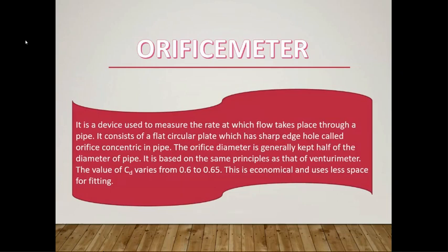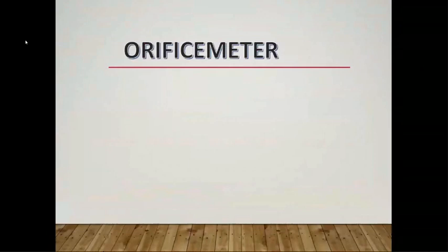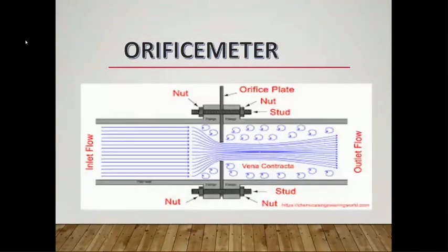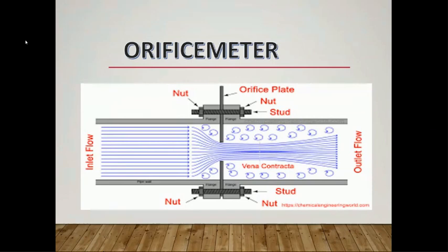The orifice meter is based on the same principle as the venturi meter. The value of Cd, the coefficient of discharge, is the ratio of actual discharge to theoretical discharge from the orifice, and varies from 0.6 to 0.65. It is economical and cheaper than the venturi meter and uses less space for fitting. In the diagram of the orifice meter, there is inlet flow and outlet flow at opposite ends, and the orifice plate at the center.